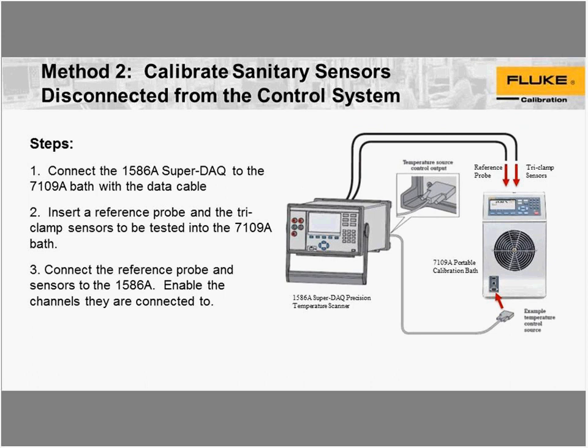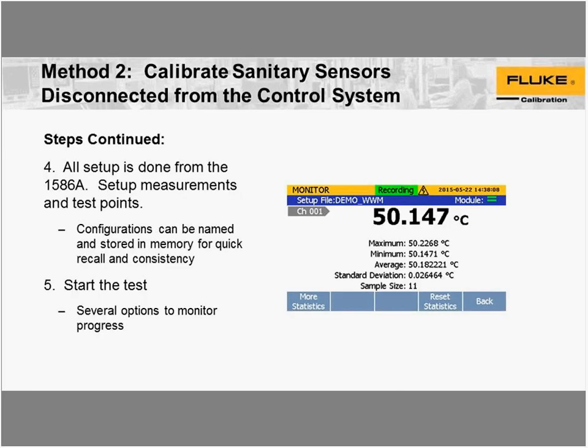Another option is to use the 1586 and its automation to open up the options a little bit more. In this case, you can connect the tri-clamp bath to the 1586A using a data cable, and also use reference temperature probes if you need to. And of course, you connect the unit under test sensor to the DAQ stack to measure it. What this allows you to do is run the calibration from the 1586, and basically it's very similar to the setup we just went through with the tri-clamp bath.